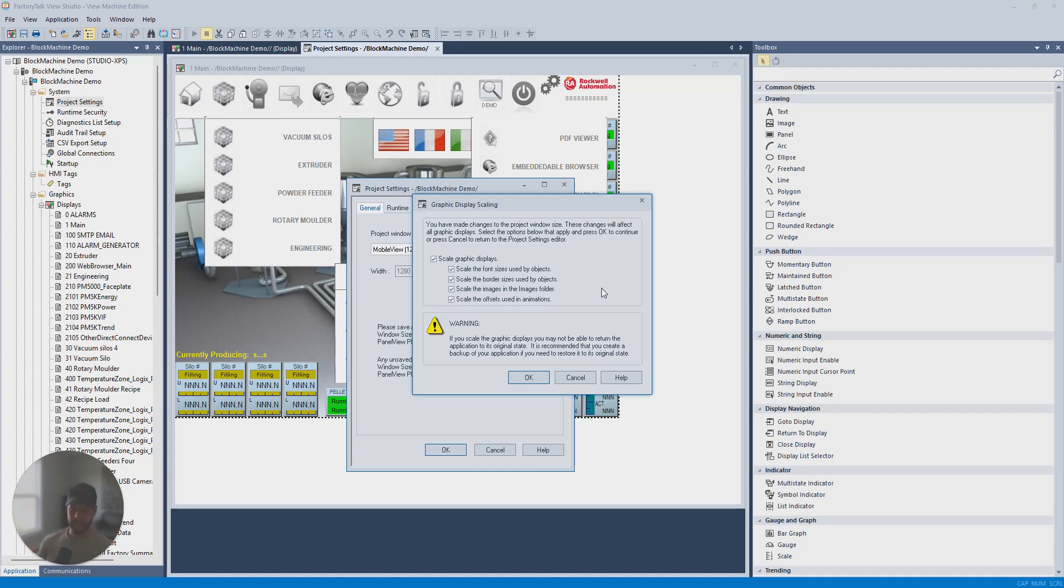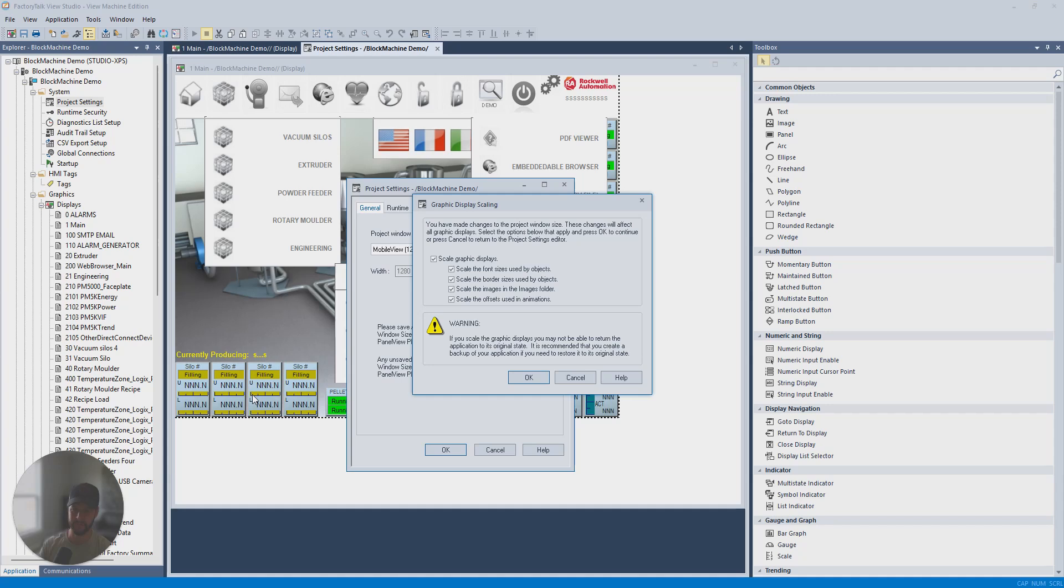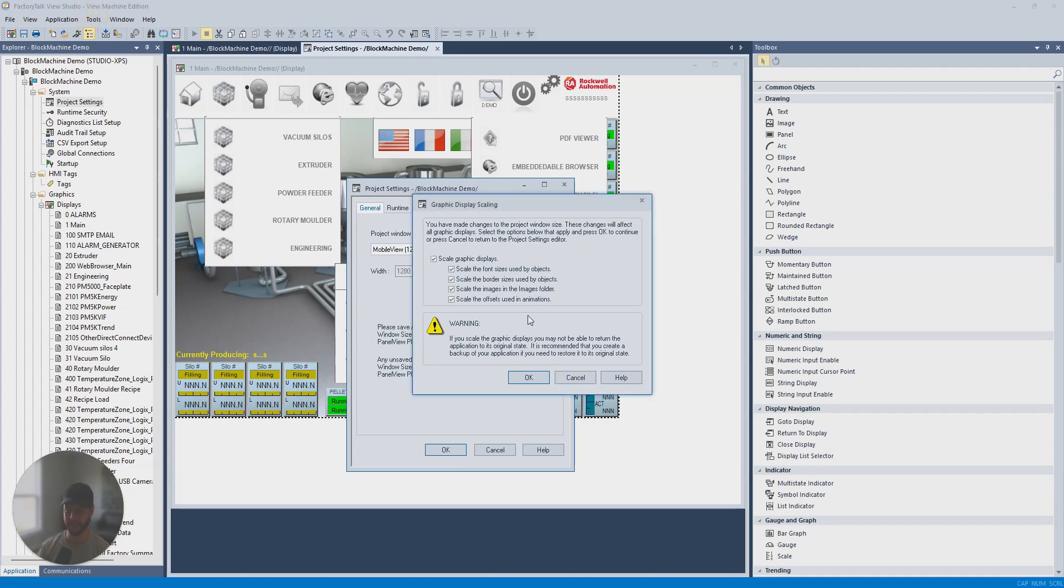I would say proceed with caution with this. If you're just testing things out and learning and playing with things, go for it and see how it works. But if you are working with an actual HMI project that you want to scale, I would not recommend it. You should always create a backup and a copy before you do this anyway. So you can always try it and see if it works. But generally, the scaling is not going to be perfect. So if you're going to do this, be sure to back up your project, which we cover in another video. But back it up so that you have a copy and you're not overwriting that existing project and ruining what you had. Because once you do this, you can't undo it.